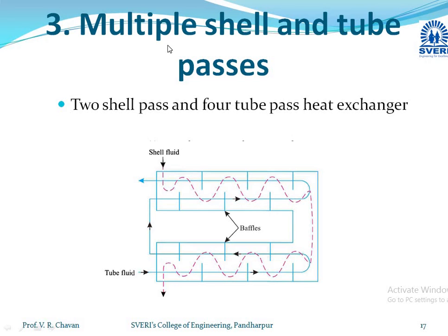The third construction type is multiple shell and tube passes. Instead of one compartment, there are multiple compartments. For example, in a two shell pass, four tube pass heat exchanger, there are two shell compartments and the tube fluid passes four times in total — two passes per shell.